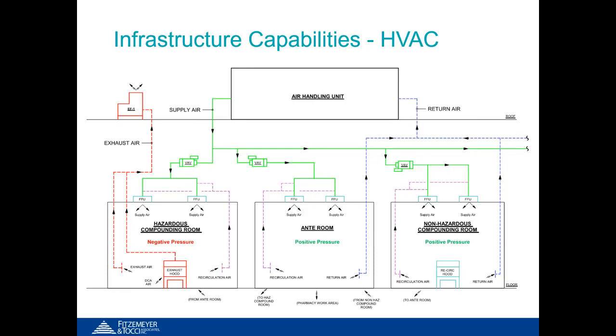This system shows what would be required typically to meet a renovated HVAC pharmacy. In this diagram, the existing air handler would have been designed for a non-pharmacy space. And in order to comply with USP, HEPA filtration and air change requirements would need to be provided for the space, but most likely would not be able to be accommodated by the existing air handler unit. To meet the requirements, fan filter units are provided. The distribution is very similar, except for supply air being ducted directly to the space. They're ducted to the return side of a fan filter unit.